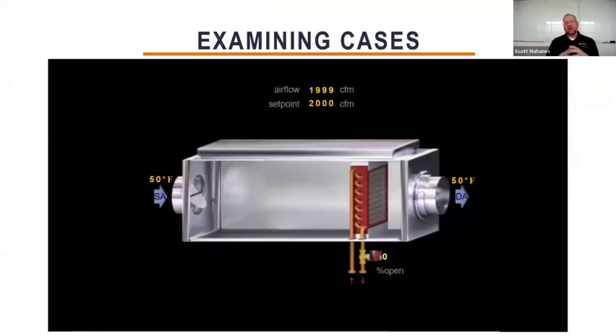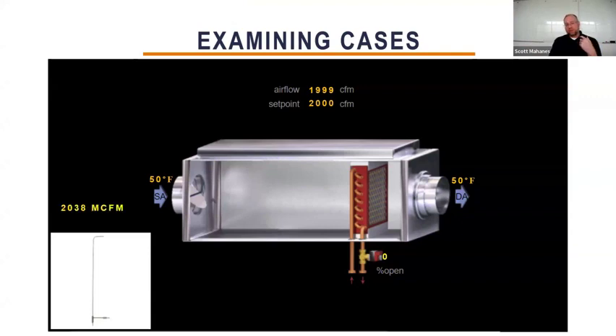Let me show you some examples of what happens in the real world with a VAV. So if I do a pitot tube traverse on the inlet of this box, and I don't use a temperature probe, my measurement's going to come out to 2038 CFM, let's say. But then I need to consider that the density is different from standard, and this is at sea level. So at 0.077 pounds per cubic foot, I need to do a correction factor for the temperature of 50 degrees. That ends up becoming a 1999 value. And so now this looks good. If the sensor believes it's doing 1999 and I'm measuring 1999 volume, we believe that this is a very good calibrated airflow sensor. But I want to show you that with a mass flow perspective, there's actually more going on than what you realize. Because if I take the volume, multiply it by the density, I get this mass flow number. If I divide that by standard density, I actually get a standard CFM value of 2077.